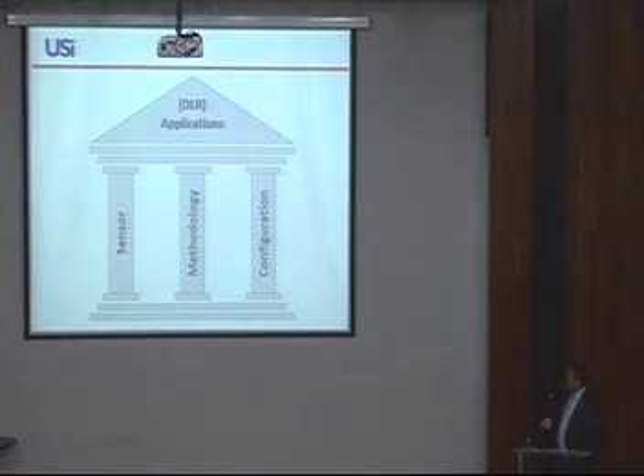Besides the choice of a sensor and the methodology, there's a third part which is important for DLR, the configuration. So assume you have a 100-kilometer line, still you have a question, where do I put my sensors? You don't put them in every tower. It's not programmable, I wouldn't say. What we'll do, we look at many things to come up at the end with a recommendation of where to put measurement points, tension or inclination, so that we make sure we cover all critical areas for all possible weather conditions. If you just assume a line has a 90-degree angle, depending on the wind direction, there will be critical sections in different parts of a line.